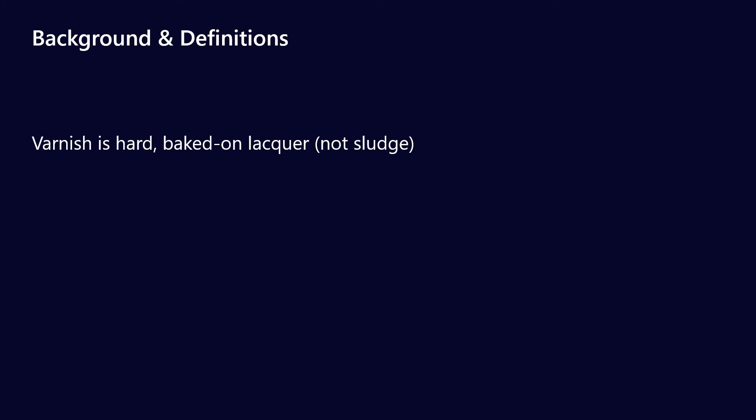Some background and definitions before we start. When we talk about varnish, we're talking about the hard baked-on lacquer — we're not talking about sludge. Sludge can probably be wiped off with a rag; varnish can't really be removed in that way. Varnish is also formed predominantly by the breakdown of the antioxidant additives — lubricant breakdown byproducts are what cause varnish.